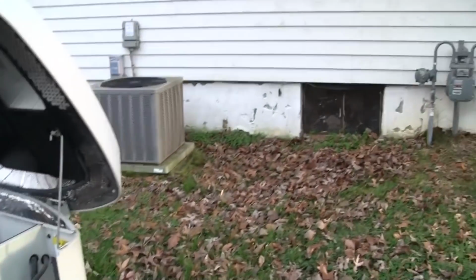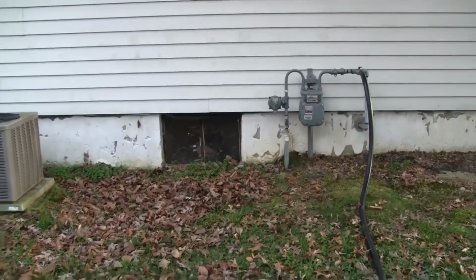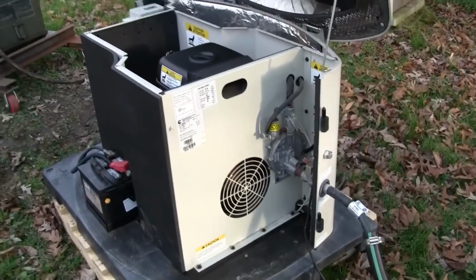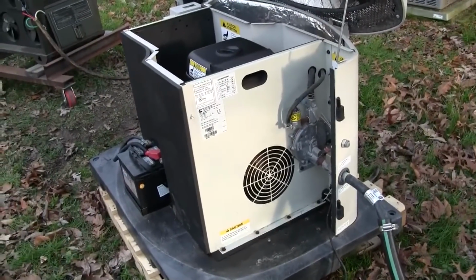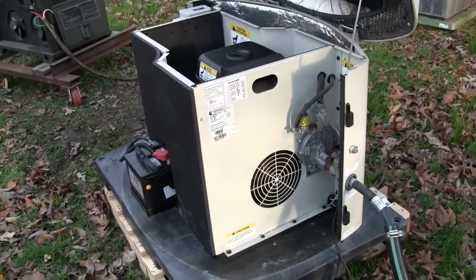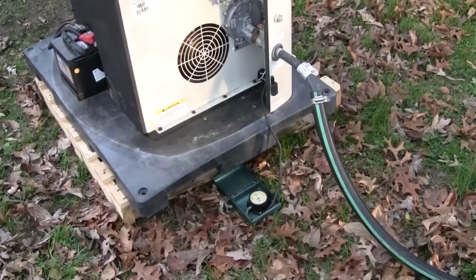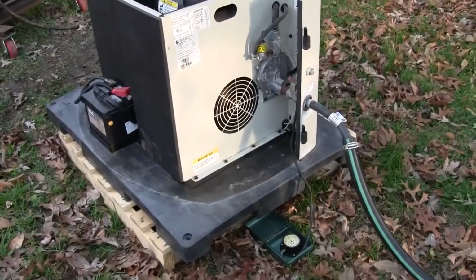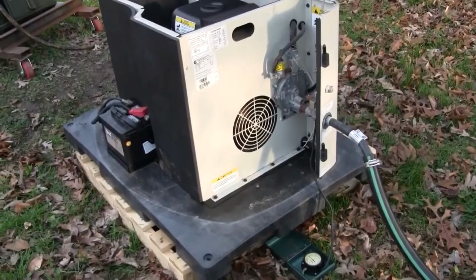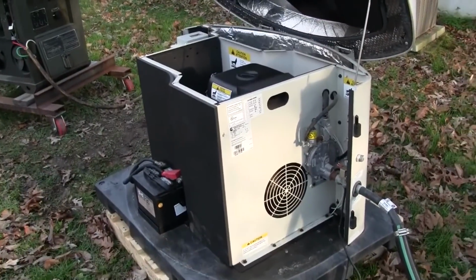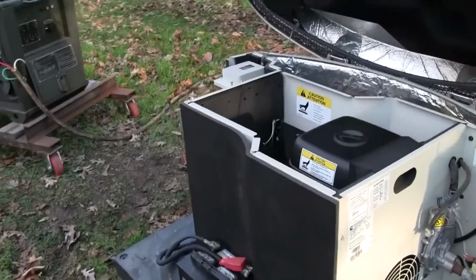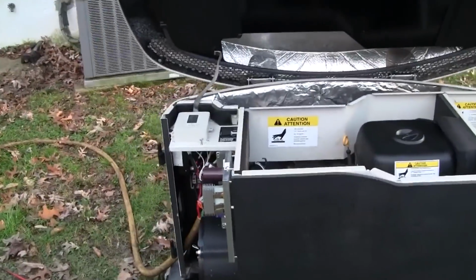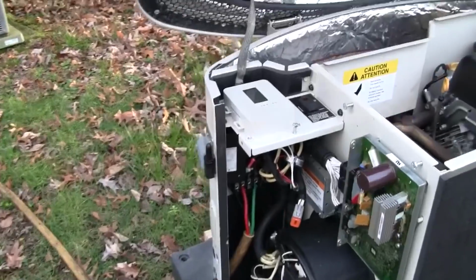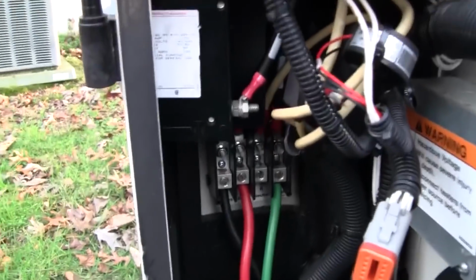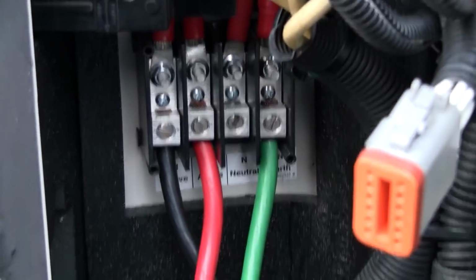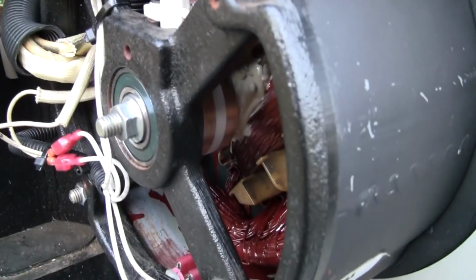So I don't know if my meter is going to have enough volume to supply this thing at full load, but if the generator starts to lose speed or run poorly, we can always look at the gas pressure gauge and say, hey, I don't have enough fuel to run it up to full power. That way we know it's a fuel supply fault and not a generator fault, that is if the thing can't carry full load. Got the load bank hooked up here. I like these units. They got a nice big terminal block here to make your connections. Everything's reinstalled and ready to go.